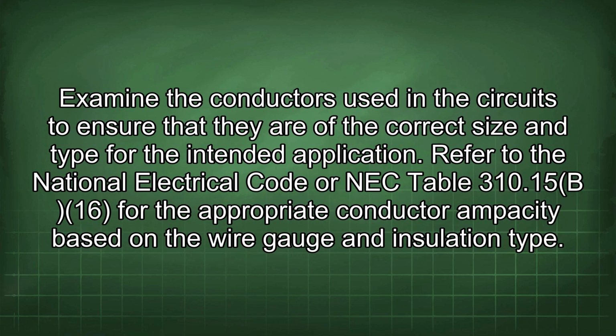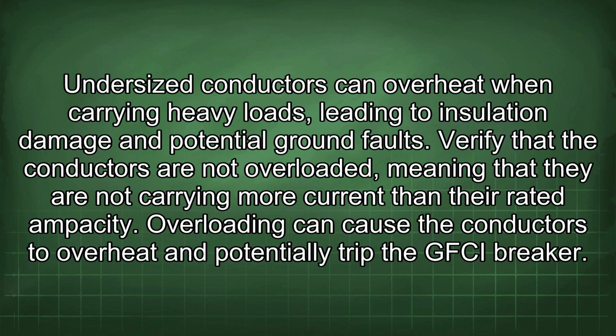Examine the conductors used in the circuits to ensure that they are of the correct size and type for the intended application. Refer to the National Electrical Code, or NEC, Table 310.15(B)(16) for the appropriate conductor ampacity based on the wire gauge and insulation type. Undersized conductors can overheat when carrying heavy loads, leading to insulation damage and potential ground faults. Verify that the conductors are not overloaded, meaning that they are not carrying more current than their rated ampacity. Overloading can cause the conductors to overheat and potentially trip the GFCI breaker.